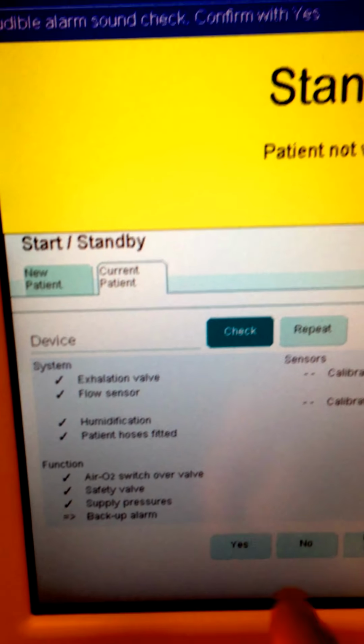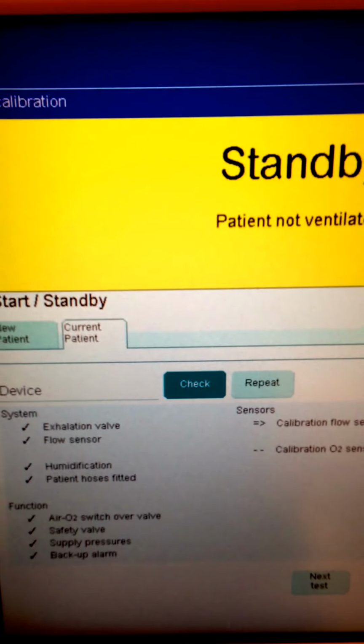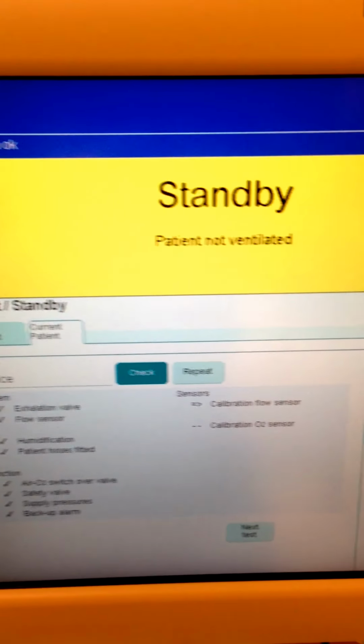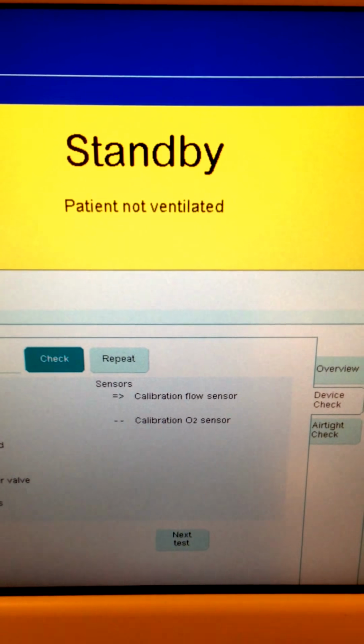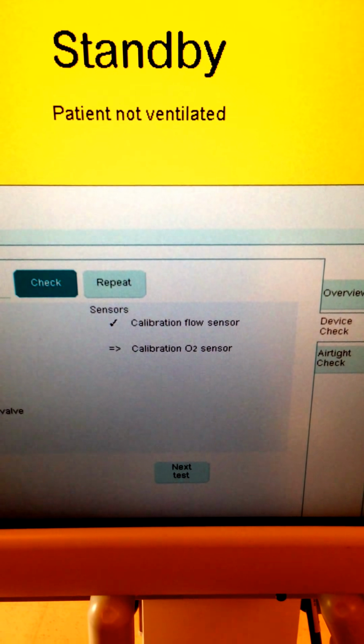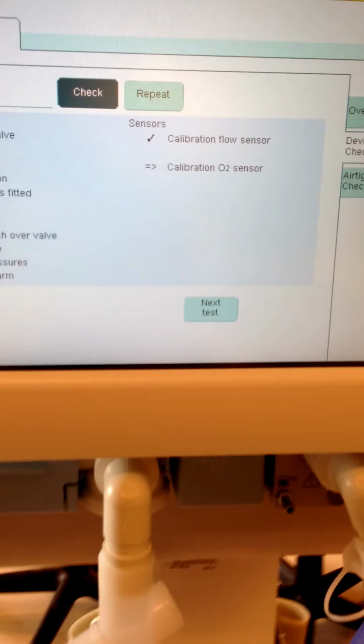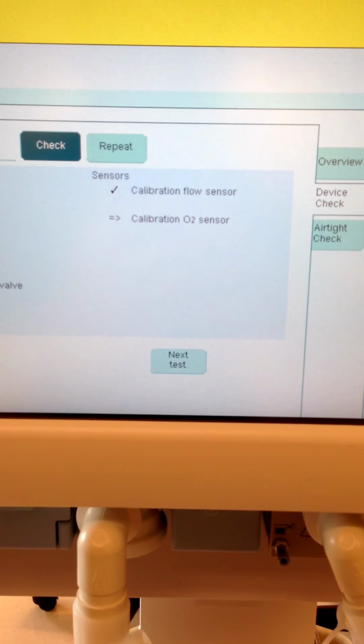Machine's going ahead without me. It's saying here, audible alarm sound, check, confirm with yes. So we're actually checking our backup alarm. Obviously we hear it. I'm going to go ahead and say yes, we hear that. It's looking at the calibration of the flow sensor now. And finally the calibration of the oxygen sensor. This one can take a minute or two, so I'm going to stop the video and then just take a picture of the end screen if everything checks out.